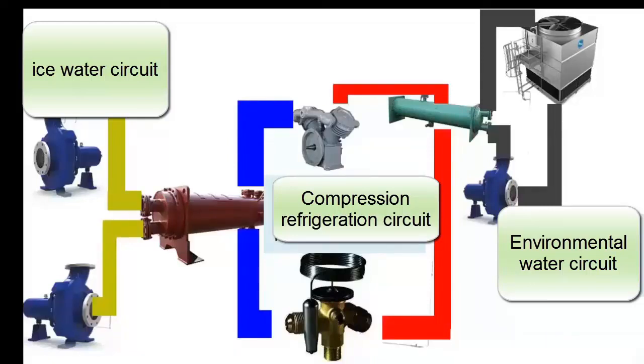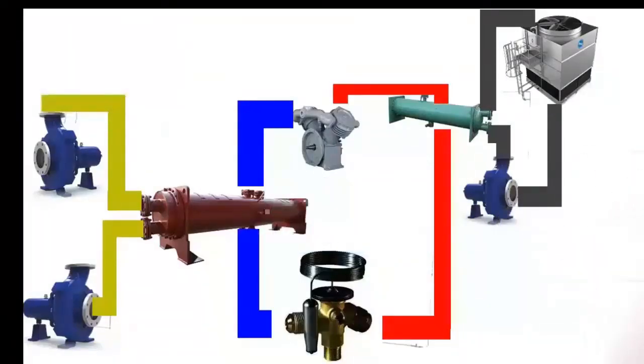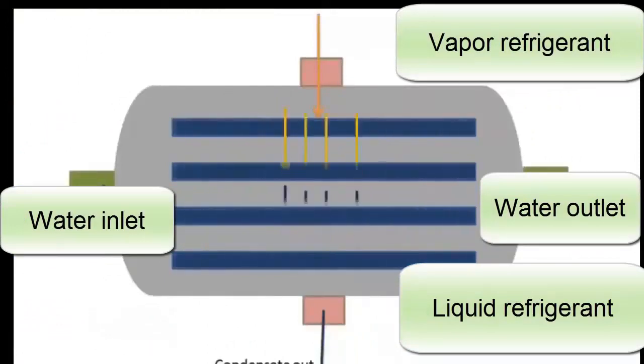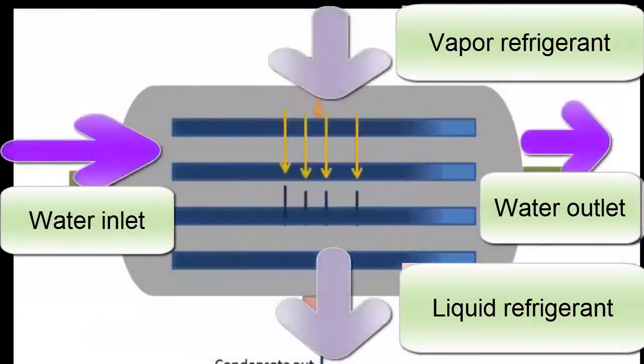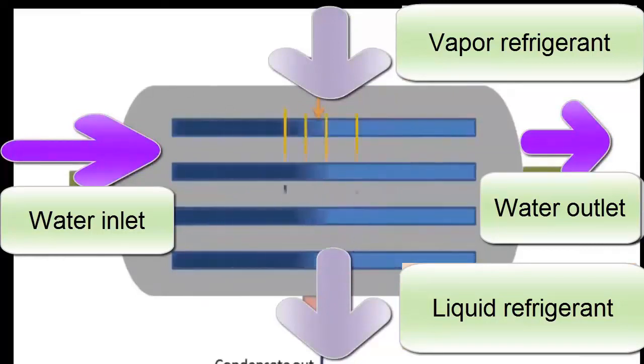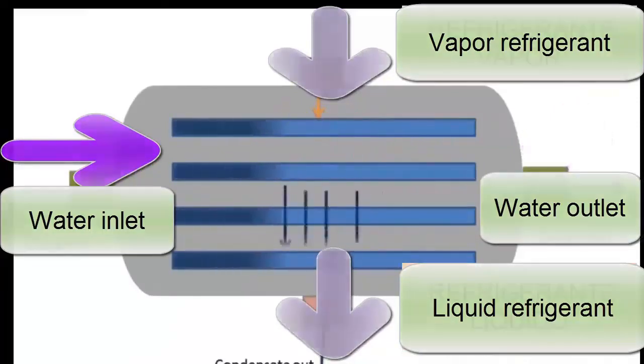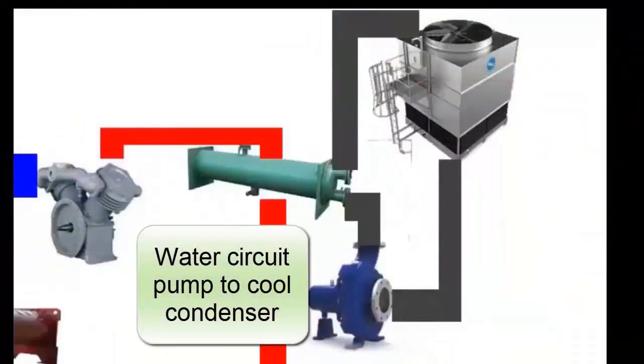These are flows that have nothing to do with each other — neither are their temperatures. This circuit to the right manages water to cool the condenser exclusively. This water does not need low temperatures; simply having ambient temperature is enough to cool the condenser, since the condenser is at a temperature above the environment. This water circuit at room temperature requires a pump we will call a condensation pump, which sends water to the chiller condenser and collects the heat from the refrigerant.